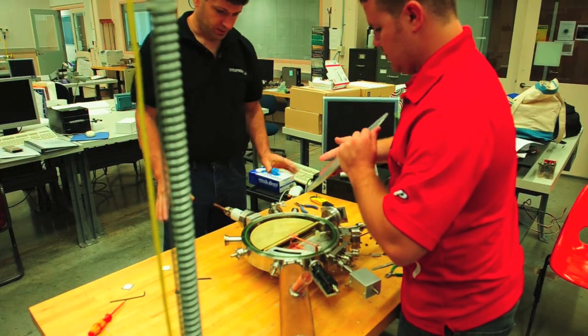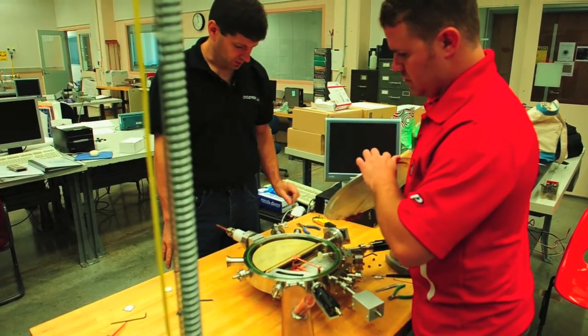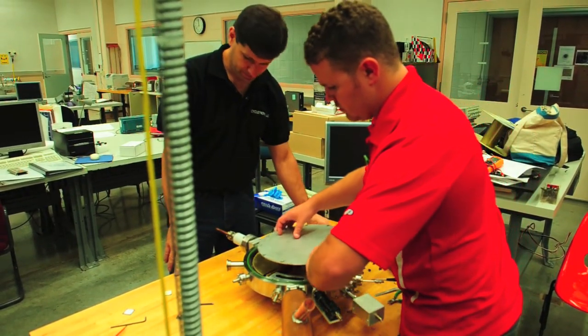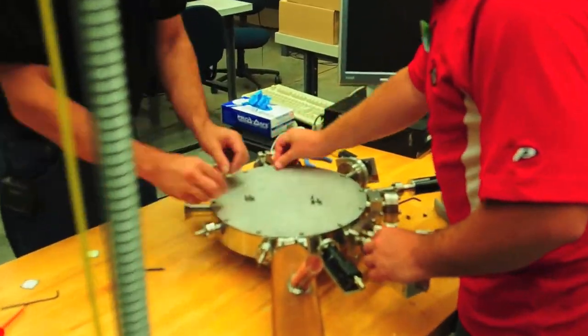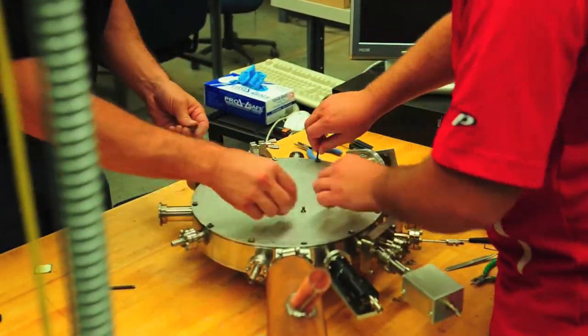Okay, so we have replaced the phosphor screens and we are going to put the lid back on and seal it up. To ensure uniform compression of the O-ring, we tighten the lid screws following a star pattern.